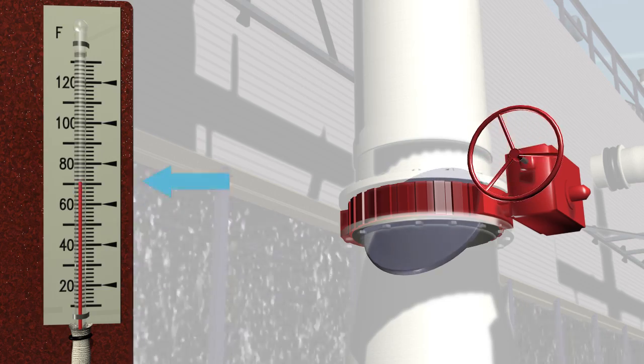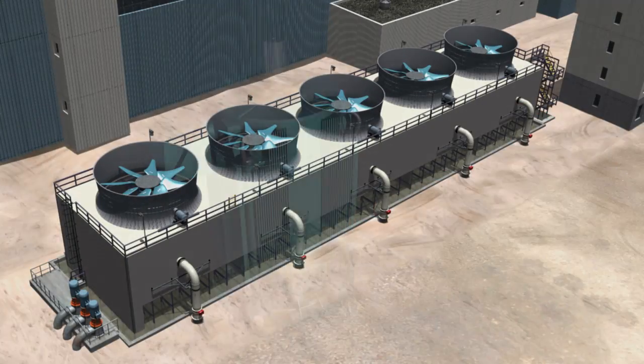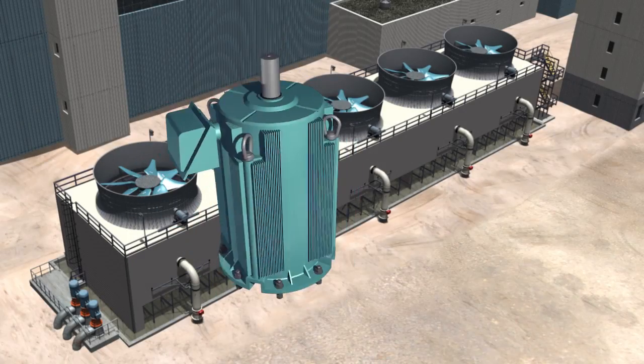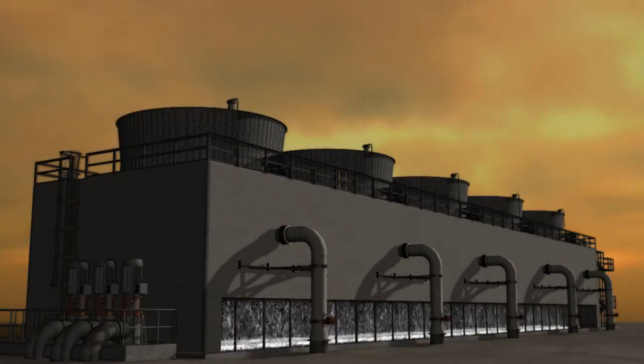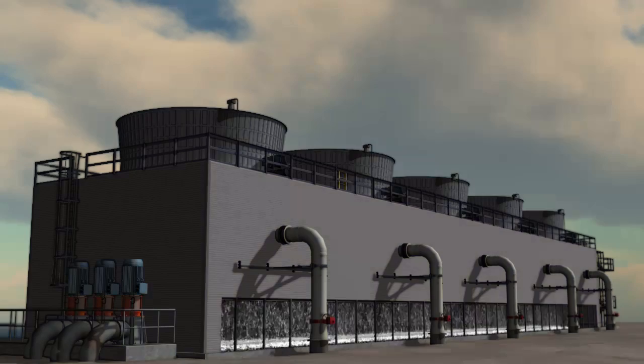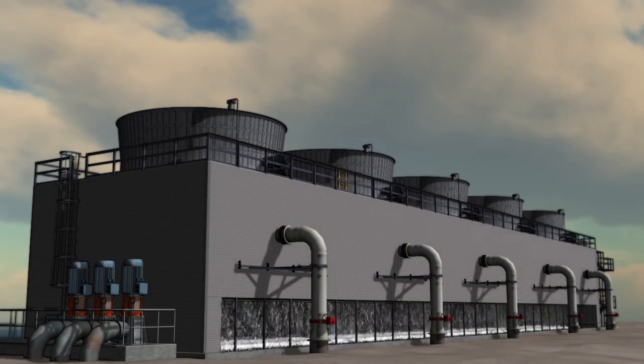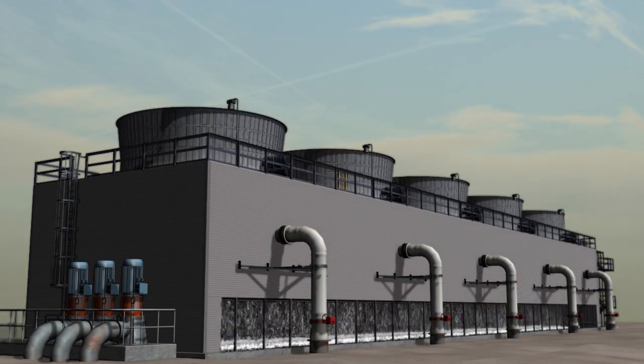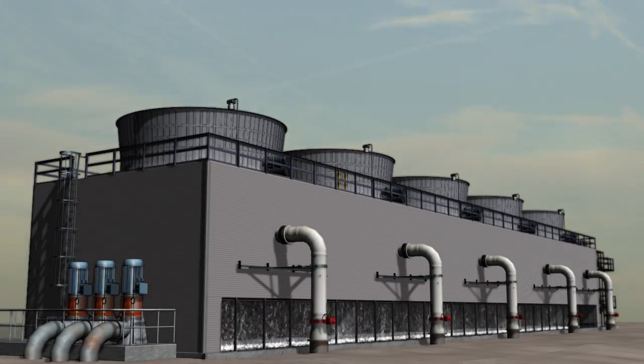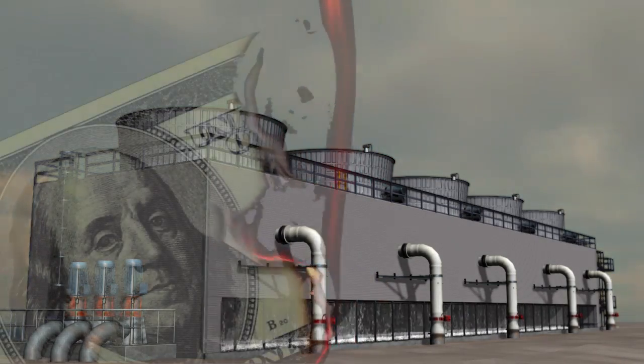Consequently, the industry has addressed only the air side of the equation, utilizing VFDs and 2-speed fan motors. On the water side of the equation, pumps are typically turned on and run all the time, 24/7, all year long. This age-old problem is the reason that cooling towers have been coined as energy hogs, wasting colossal amounts of water, energy, and your money.